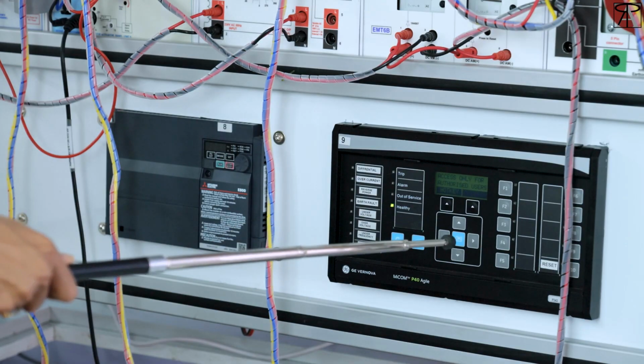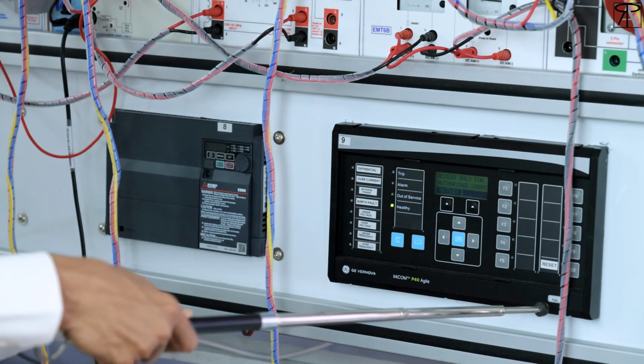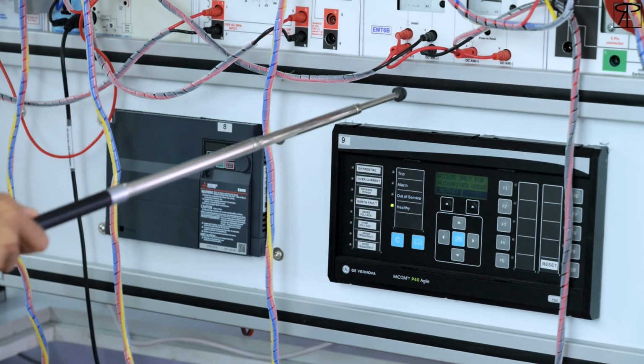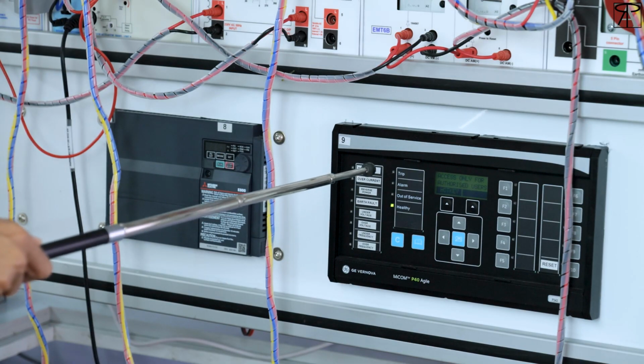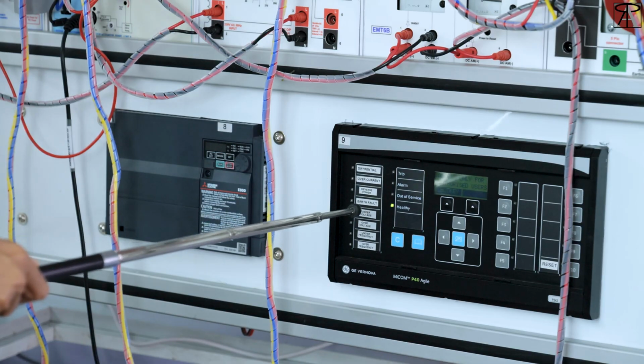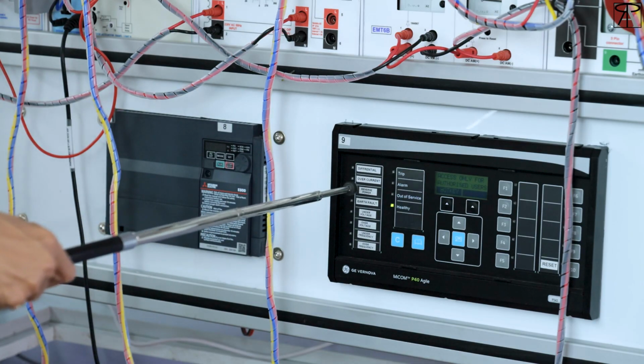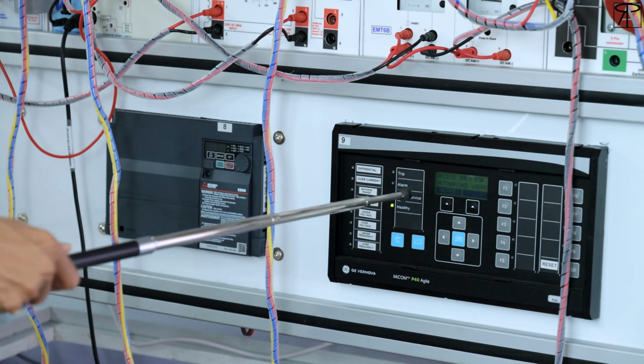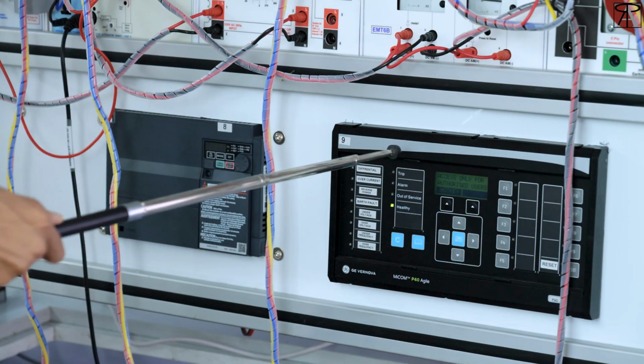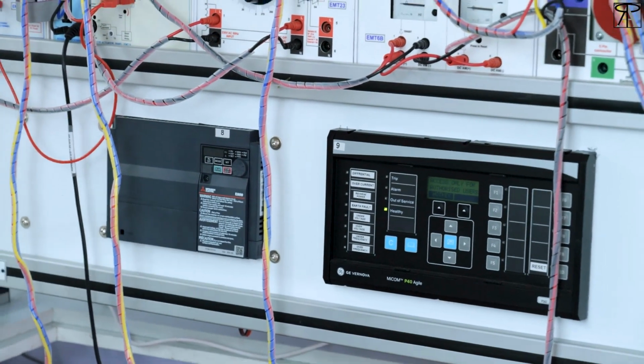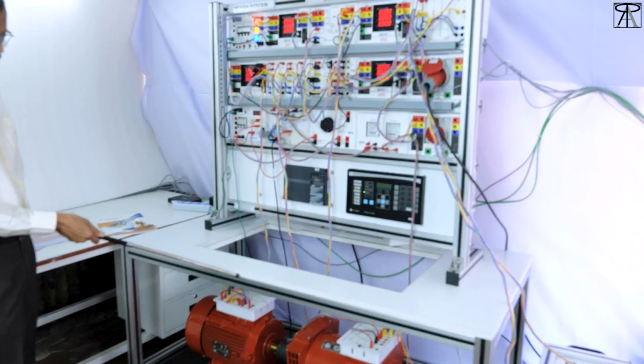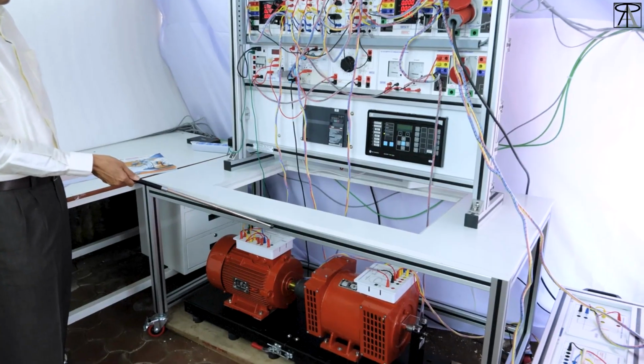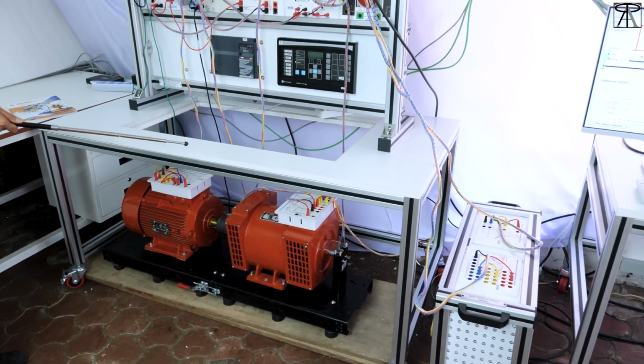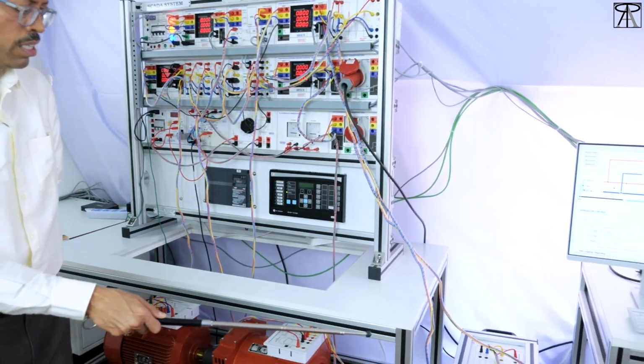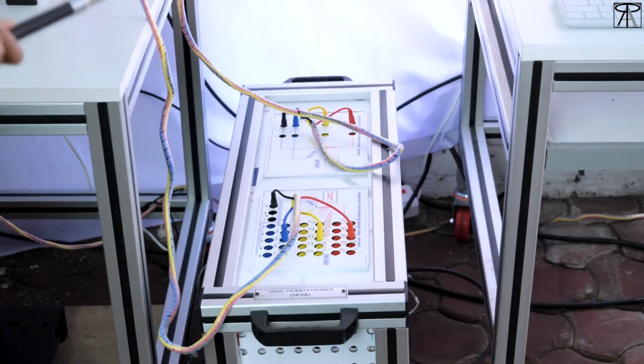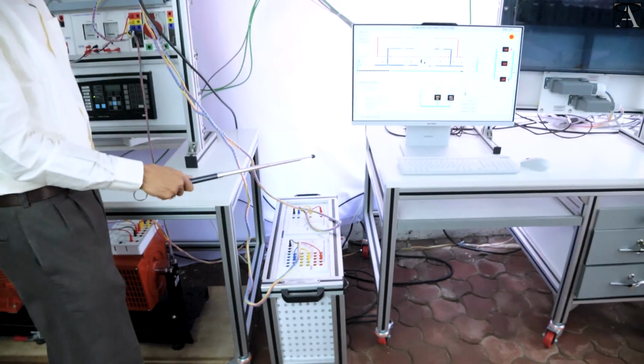We have used a GE make relay, the generation protection relay, model P343. It has differential protection, overcurrent protection, reverse power, earth fault, under voltage, over voltage, under frequency and over frequency. All voltages and currents can be measured on the display, and faults can also be seen on the display. This setup will come with aluminum profile tables. These tables are very long standing and have no corrosion, unlike metal tables. And this is the generation transformer for the grid, for the supply of synchronization and protection.